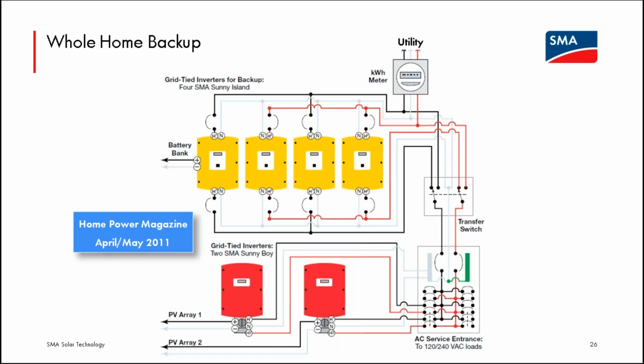The grid will charge the batteries for the Sunny Island while it is present, and as soon as it fails, you see this diagram, the transfer switch is switched over to where the Sunny Islands now are powering the full home panel, and now all of the PV power from those two Sunny Boys is available on that home panel.